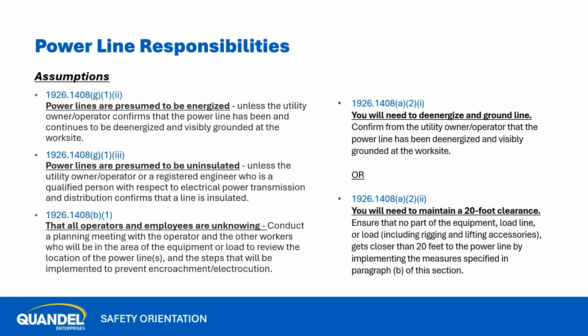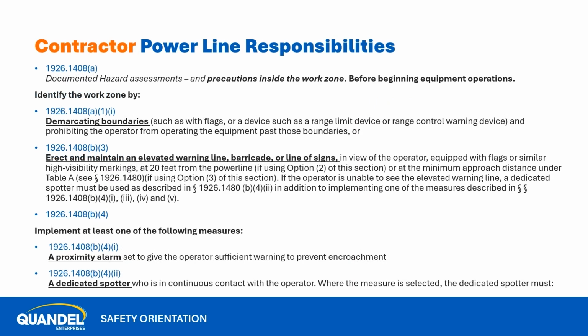You should assume that all power lines are energized and all power lines are uninsulated. It should be assumed that all operators and employees are unknowing and should be informed of power line location. Take steps to prevent encroaching and electrocution. You need to confirm the line is de-energized and grounded, and you must maintain a 20-foot clearance. Contractors are responsible for demarcating boundaries with flags or a similar method. They must also erect and maintain an elevated warning line, barricade, or line of signs 20 feet from the power line. Either a proximity alarm or a dedicated spotter should be used to monitor the danger zone.